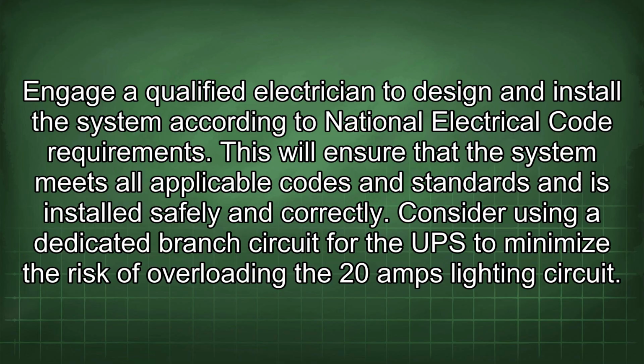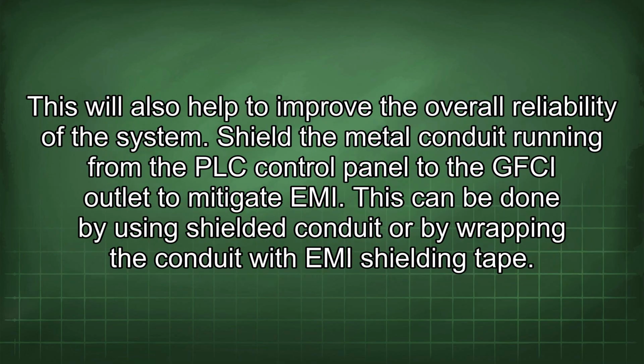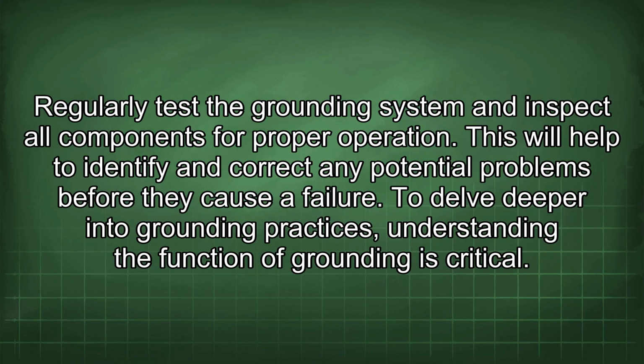Engage a qualified electrician to design and install the system according to National Electrical Code requirements. This will ensure that the system meets all applicable codes and standards and is installed safely and correctly. Consider using a dedicated branch circuit for the UPS to minimize the risk of overloading the 20 amp lighting circuit. This will also help to improve the overall reliability of the system. Shield the metal conduit running from the PLC control panel to the GFCI outlet to mitigate EMI. This can be done by using shielded conduit or by wrapping the conduit with EMI shielding tape. Regularly test the grounding system and inspect all components for proper operation. This will help to identify and correct any potential problems before they cause a failure.